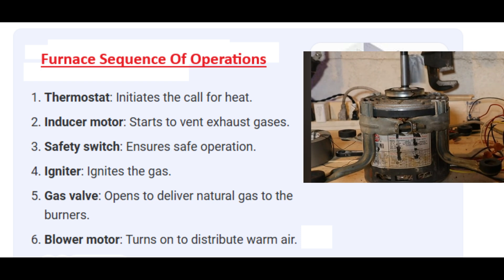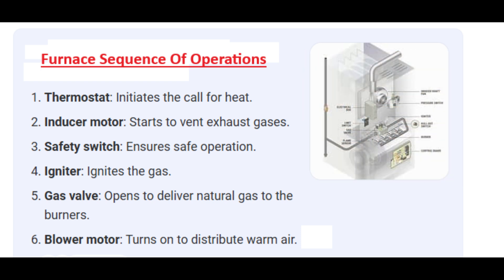In knowing that sequence, if I go on a job and the furnace goes through that entire sequence, then I know if it shuts down after that point, that might be a good time to test the thermal overload — because a thermal overload switch has to reach a certain temperature in order to open up the circuit and shut the system down. So the furnace has to run for a little while to hit that temperature. If the furnace goes through its whole startup sequence and a couple of minutes after it's running it shuts down, that's my clue to start with the thermal overload switch.